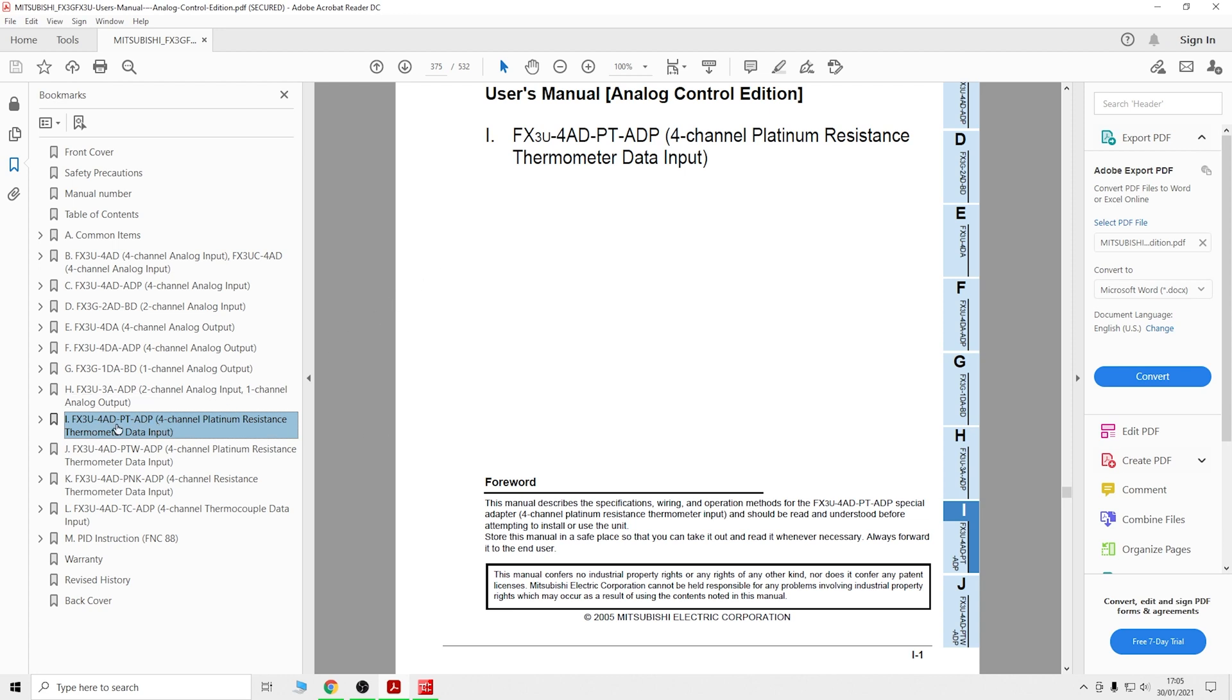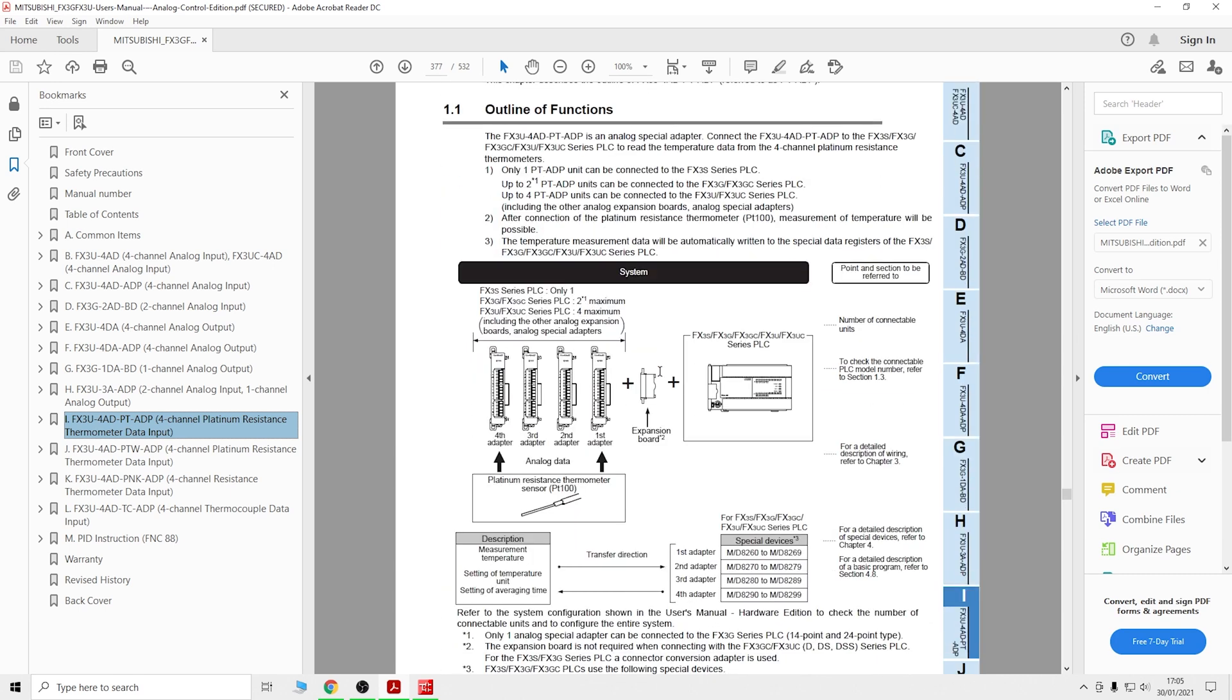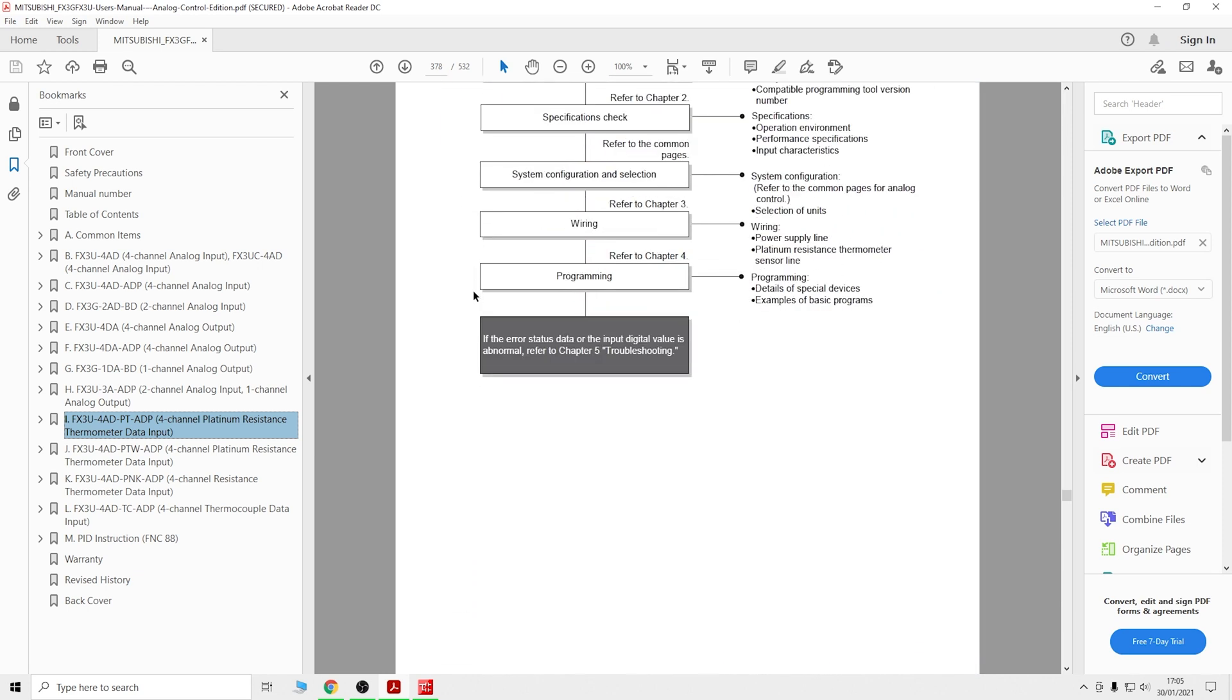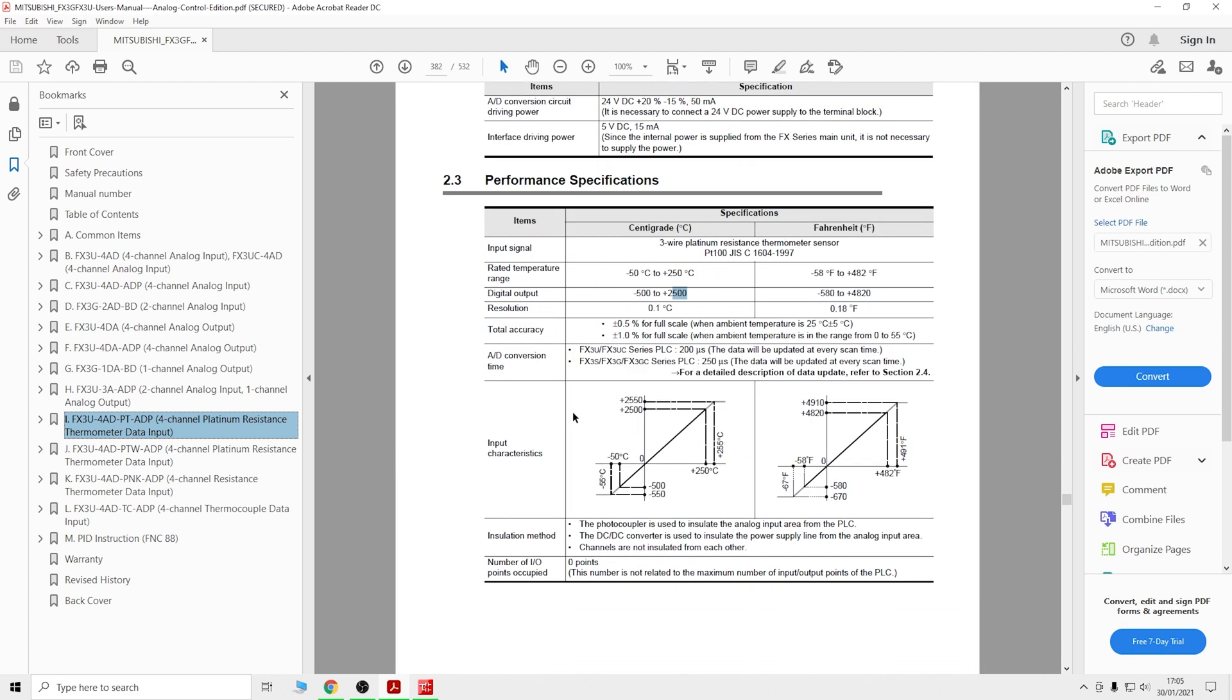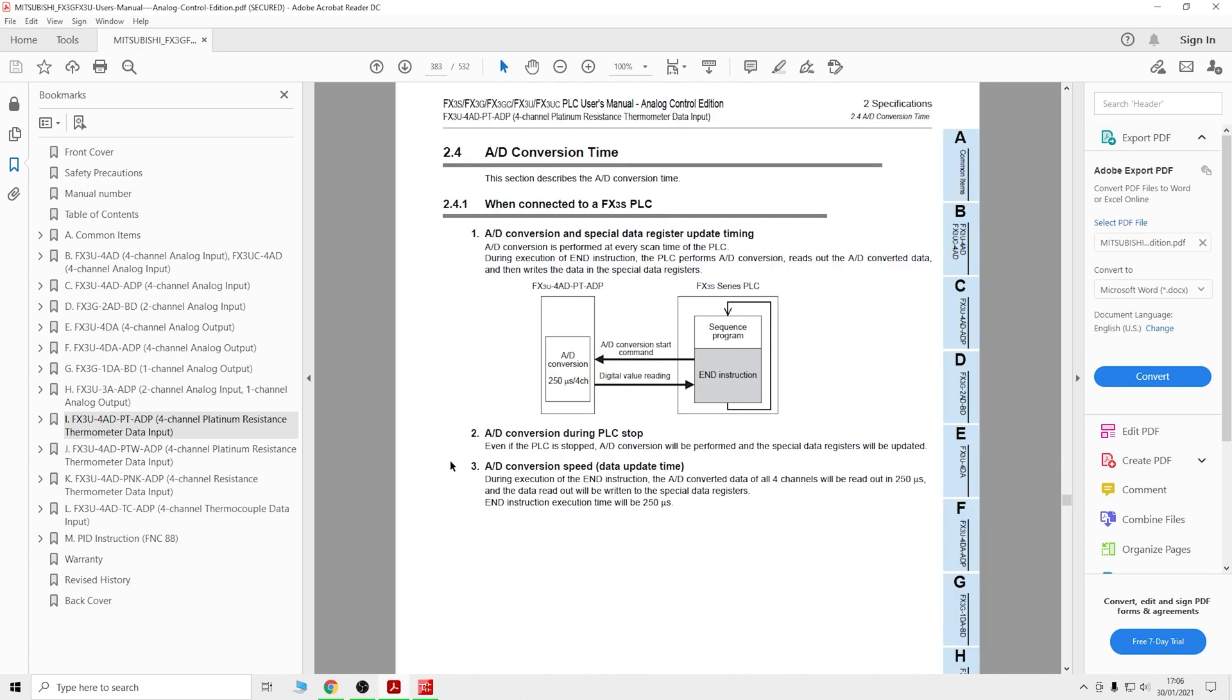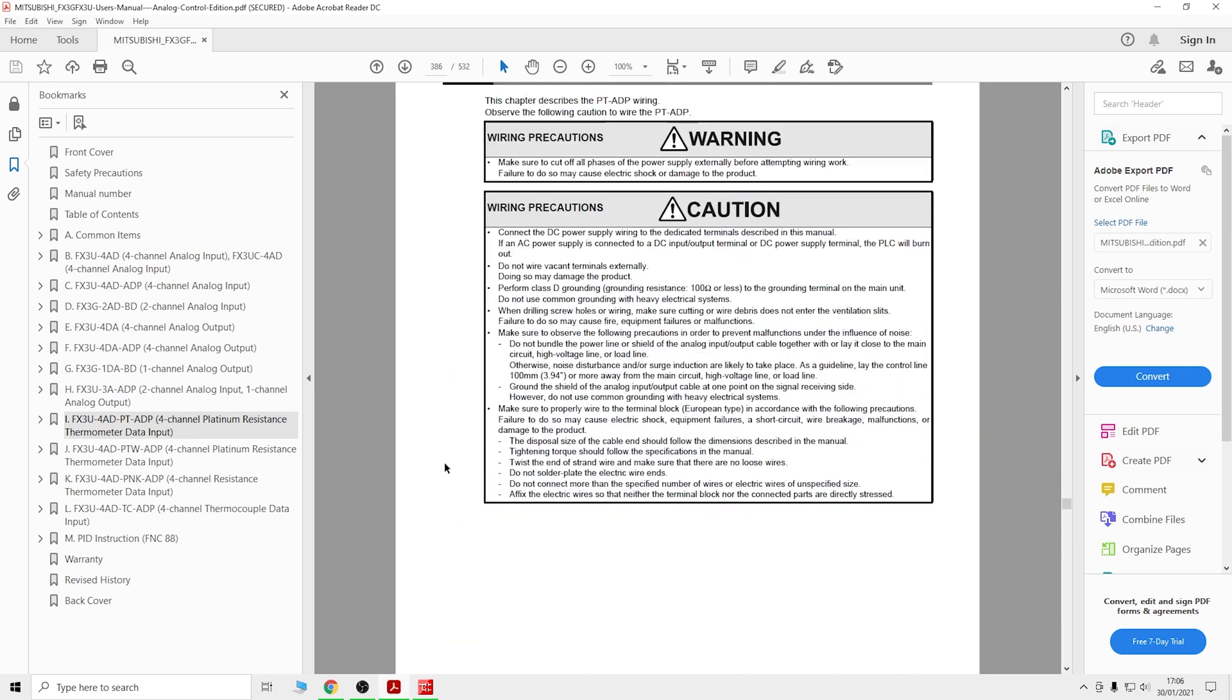As you can see, only one PT ADP unit can be added to FX3 series. Looking at the general specifications, the rated temperature range is between minus 50 and plus 250 Celsius, or in Fahrenheit. Mitsubishi has done all the hard work - the digital value reads as minus 500 for minus 50 degrees and plus 2,500 for plus 250.